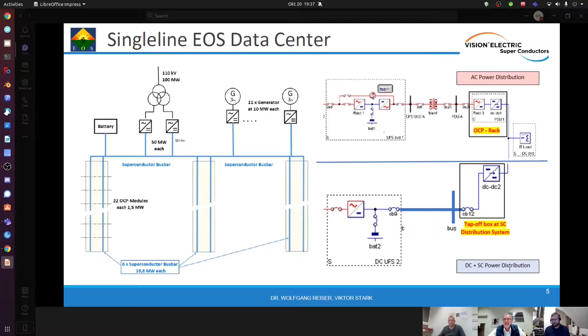Perfect, Victor. You want to explain what we see here? Yes. I already said that you can put more servers on the space. The other thing, if you think about it from the beginning to the end, is that you have one line from power generation to the rack. If you have a tap-off box with only a DC conversion step, where you can feed all the servers, you do not need the power shelves within the servers. You can replace the power shelves and put servers in there directly. This is also a huge advantage.